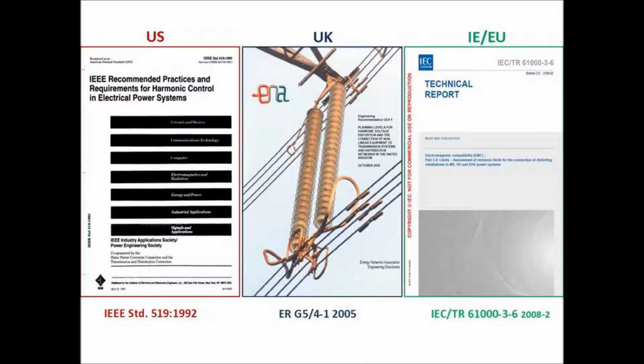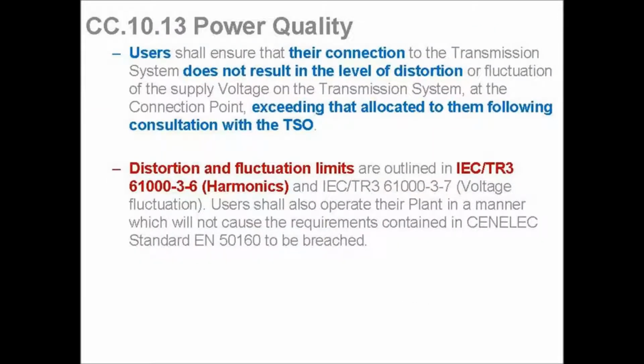The IEC one tries to do something similar to the US one, whereas it puts the onus on the user and specifies a voltage distortion limit. It prorates it out amongst a cluster or a group of users if there is more than one user at a facility. So it tries to be a little bit more fair than just first come, first served in the UK. So I suppose just to talk about the grid code, it is the rules we go by.